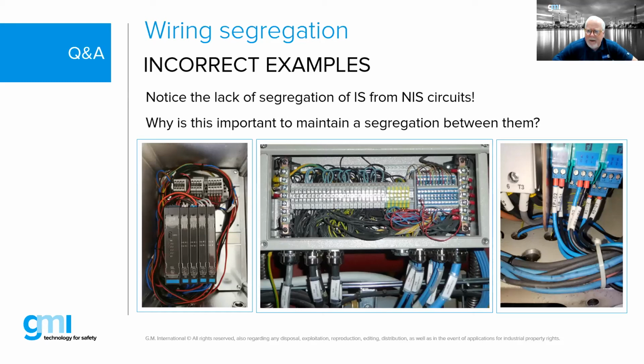On the one on the left-hand side, when we start looping around our individual core conductors, we violated that 50 mm separation, right? If we look on the panel in the middle, it looks like the cables on the right-hand side are marked light blue, so that's telling me it's IS. We have certainly segregation between the cables, but once we get inside the panel, now all of a sudden all hell breaks loose.